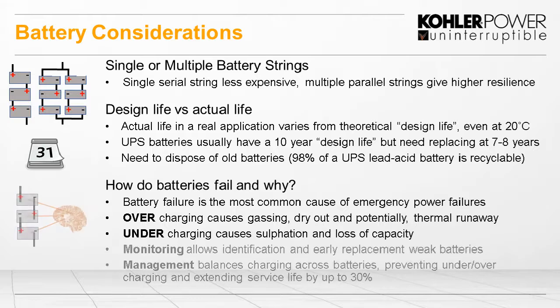So, we need to monitor these batteries so we can see if they're being over or undercharged and if they are getting weak or high impedance. So if we monitor them, we can see this happening and we can replace any weak battery early enough to prevent a failure when it's actually needed. But to prevent over and undercharging, you can put a management system on batteries, and this will prevent that over and undercharging, and it can, in some cases, extend that service life by up to 30%. But the main thing is it makes a much more reliable, resilient battery solution for you.